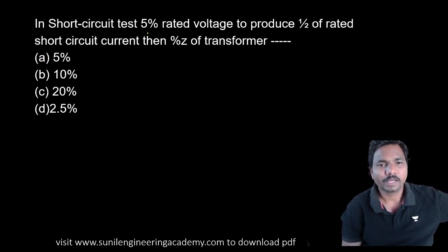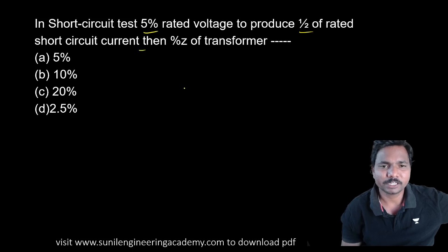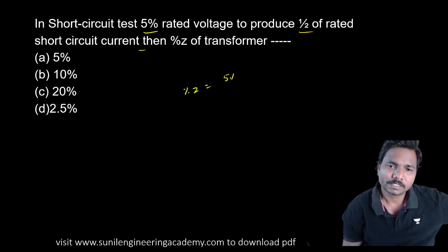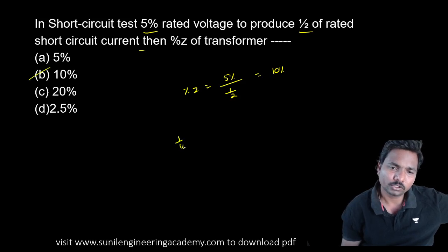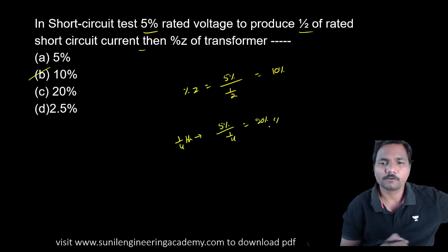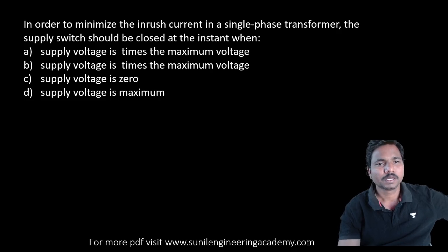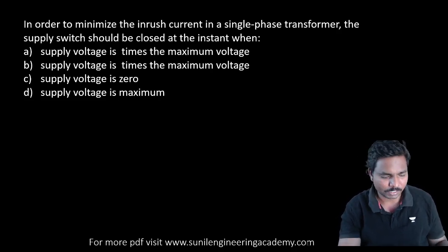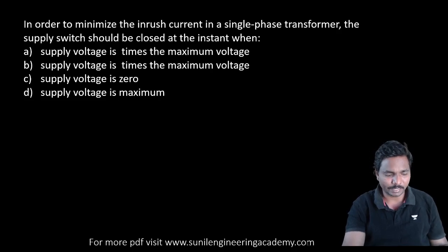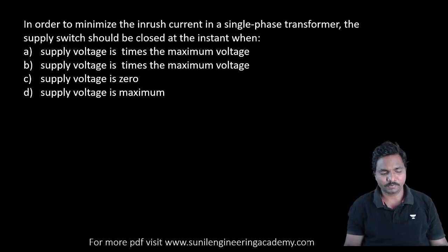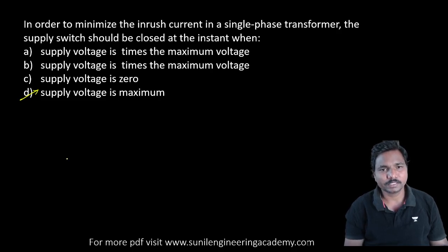Coming to the next question: 5% rated voltage to produce half of the rated current. What is the percentage Z? Just now I have given 5% by rated current. Half of the rated current means 10%. If they are asking one by fourth, then 5% by one by fourth, that is 20%. Like that we have to give the answer. In order to minimize the inrush current in a single phase transformer, the supply should be closed at the instant when dash. Whenever the supply voltage is maximum, in that case we can minimize the inrush current.